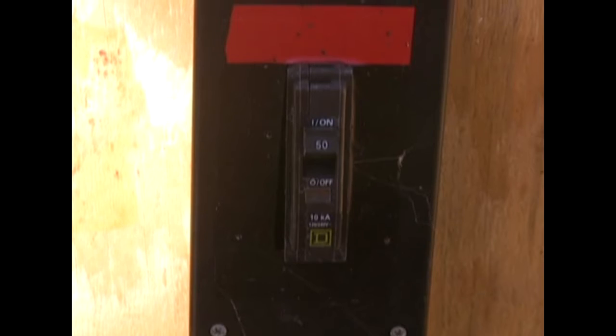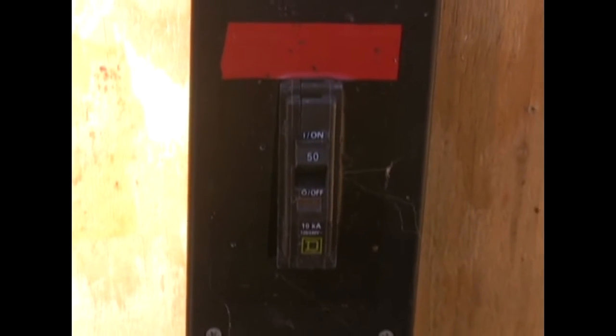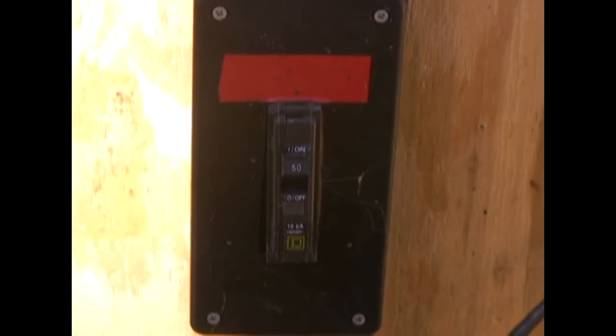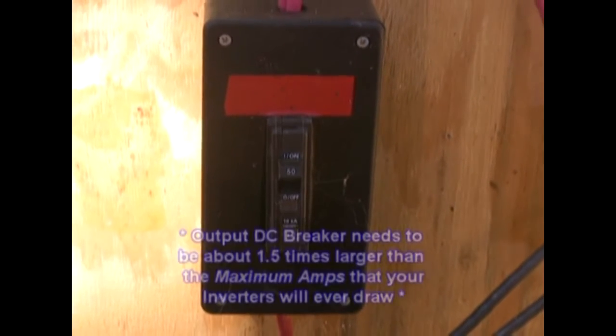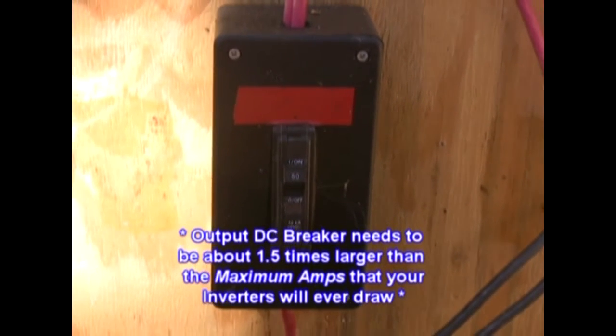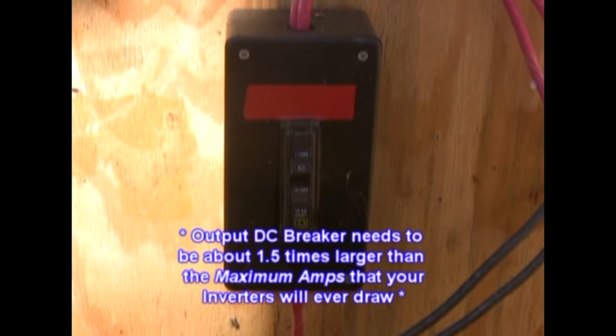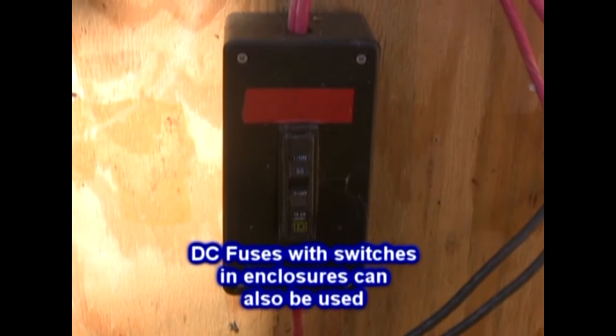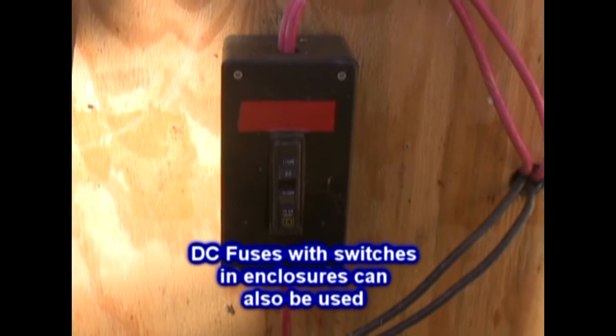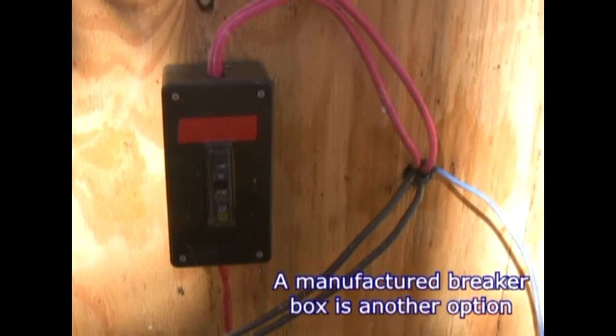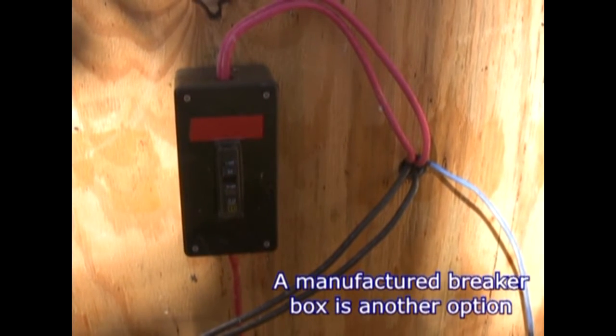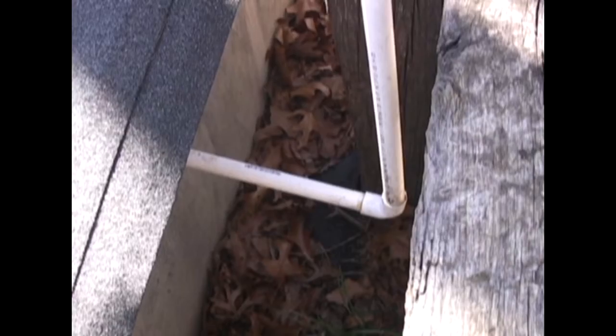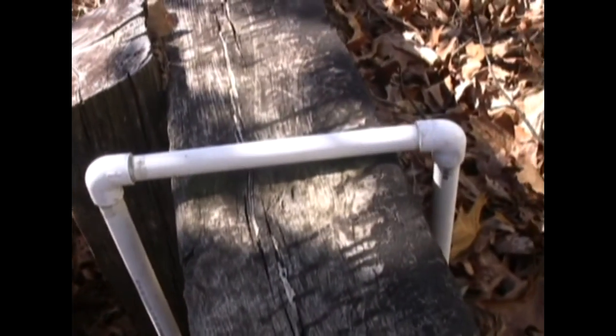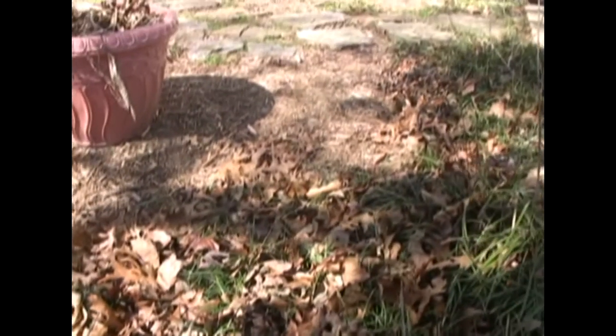On this small system, I used a single 50 amp breaker coming out, all I needed to feed the inverters, since I was never going to draw more than 50 amps, and put it into a small project case. A big piece of red tape on top indicates on. This is a way of enclosing one of these simple breakers, with the wiring going out the back of the box - our power output from the output breaker, a PVC tube over this railroad tie wall, buried in the ground, going back up to the house.